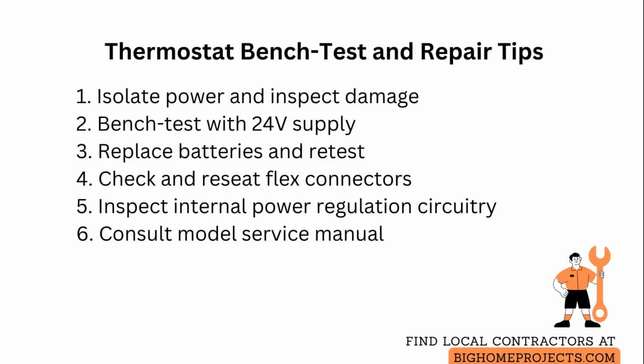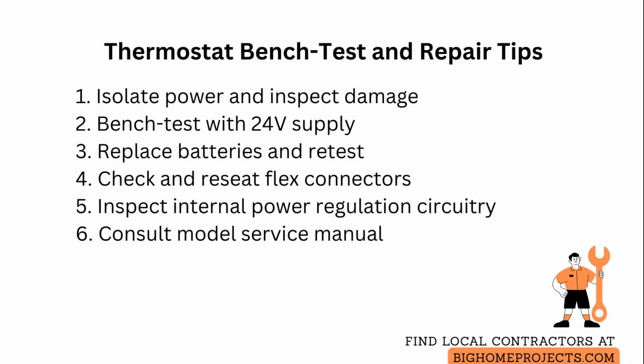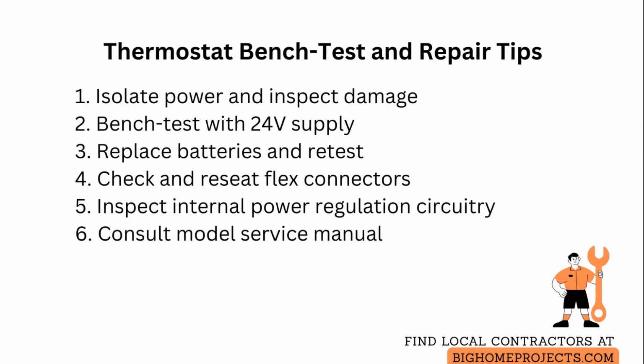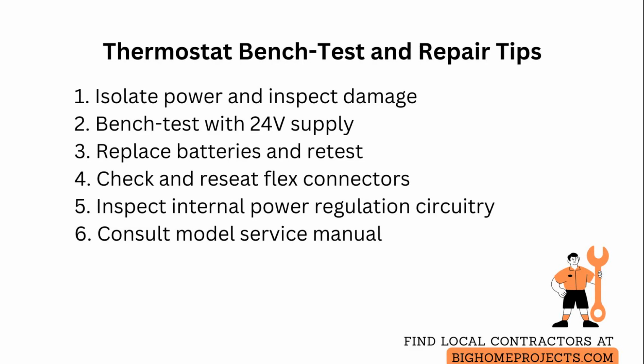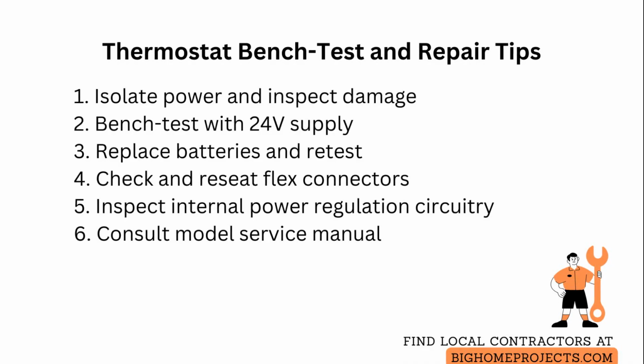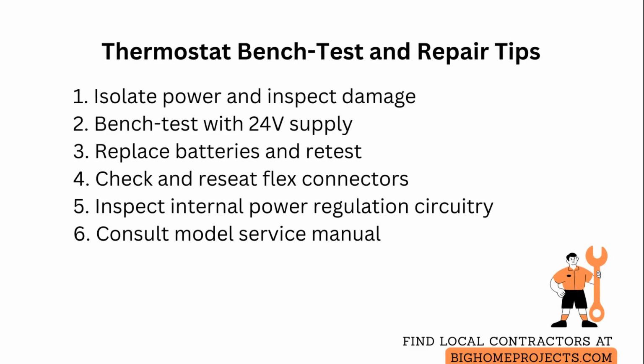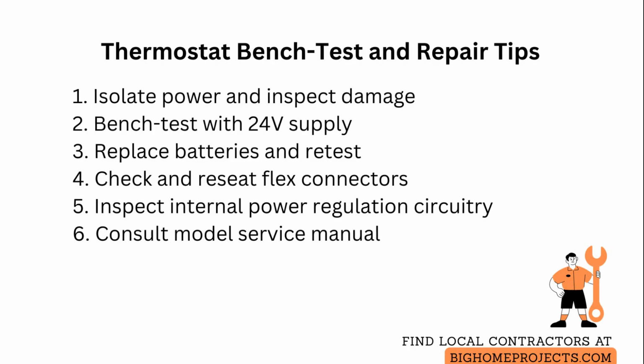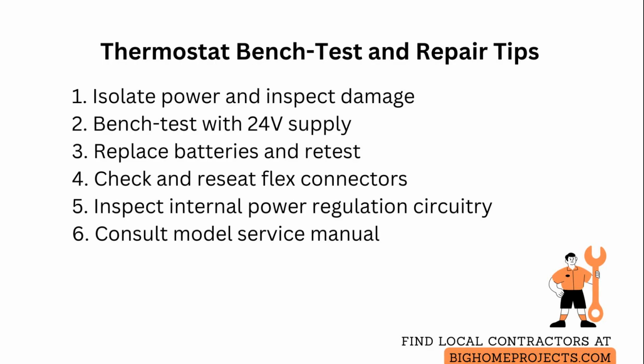A functioning display with no response to button presses suggests a failed input matrix or microcontroller. If the display is blank while the bench supply is present, the internal power regulation circuitry or backlight driver may have failed, requiring replacement. For battery-backed models, replace batteries with fresh, high-quality cells and recheck. Some thermostats will present full terminal voltages to the system, yet still draw insufficient current for internal operation when batteries or internal regulators are compromised.